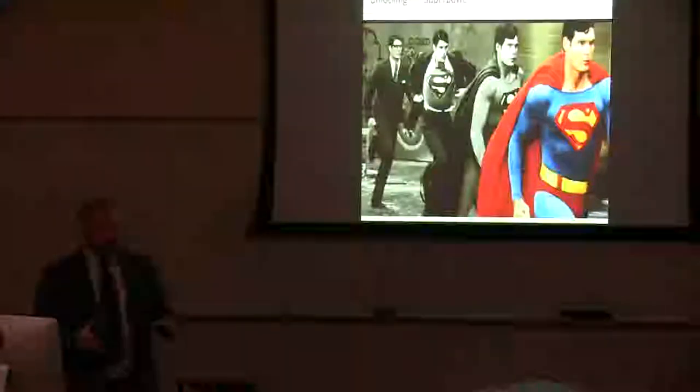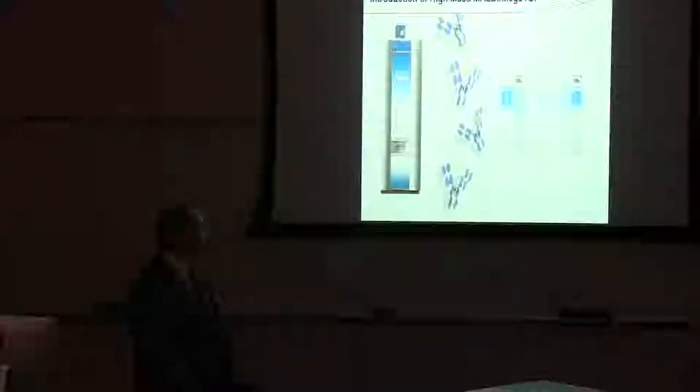So, when you're talking about your standard MALDI, I kind of like to think of the megatop as like the superhero MALDI, and that it unlocks some of the powers that a standard instrument wouldn't have. So, just as Clark Kent changes costume into Superman, you've got to do a little costume change for the megatop. So, we've exchanged the panel, but we also have the high mass detector sitting on top. And really, what you're able to do is to easily exchange between the standard mode of operation using a typical electron multiplier detector, and the CovalX detector, just using a tablet device that you can click a button, and it'll switch in and out of position.